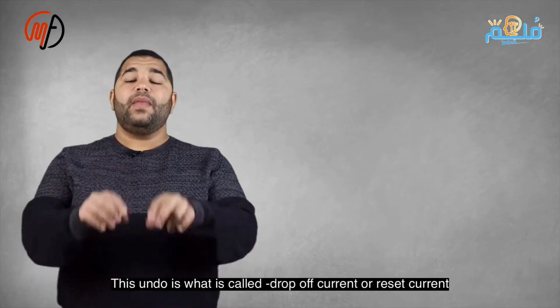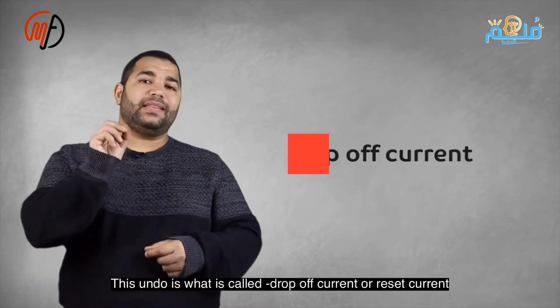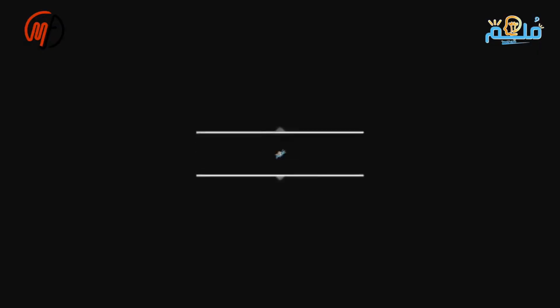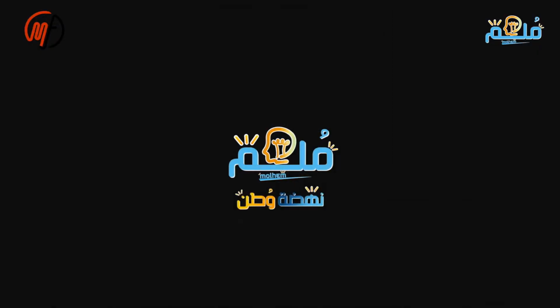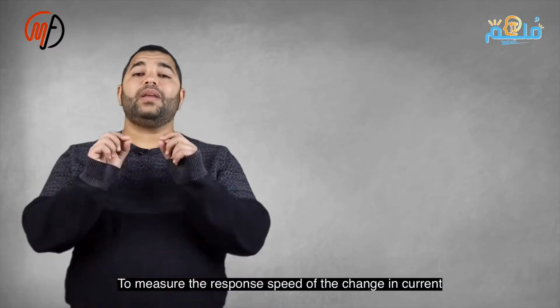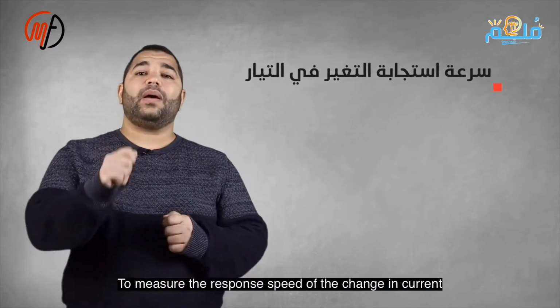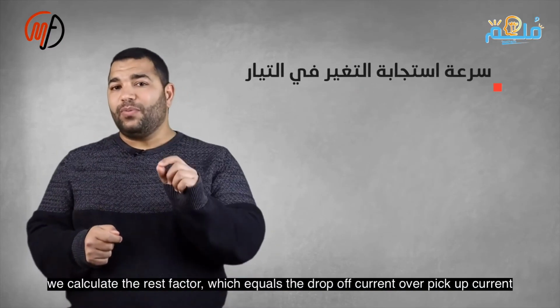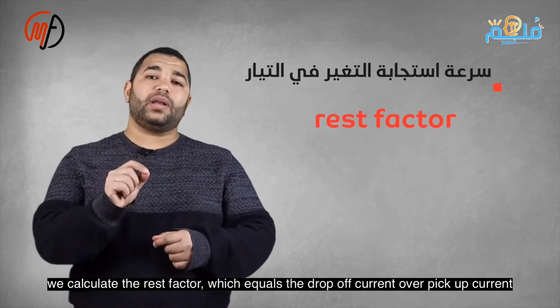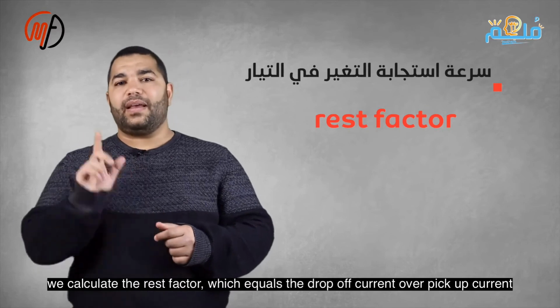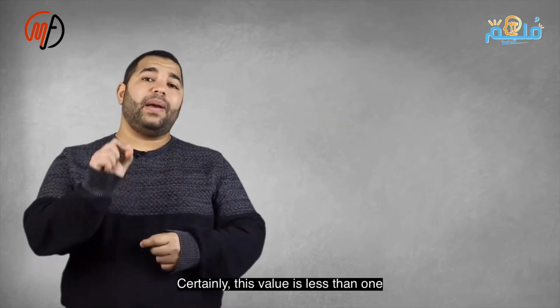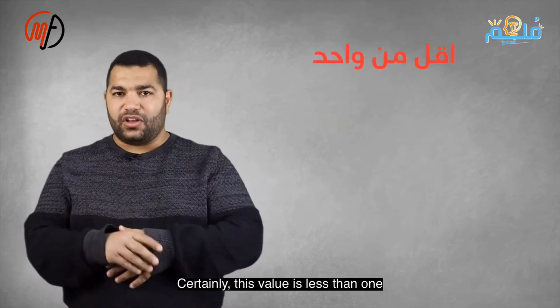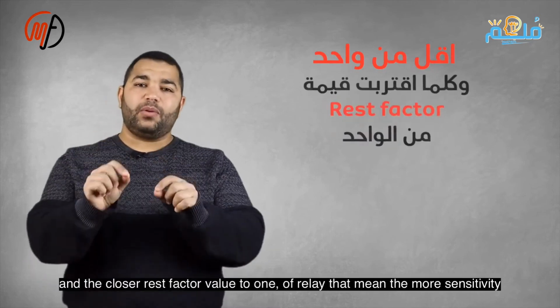The second test for the overcurrent and earth fault relay is the timing test. To measure response speed to current changes, we calculate the reset factor, which is drop-off current over pickup current. This value is less than 1. Closer to 1 means more sensitivity. If current is less than pickup current, even by 0.001, the relay should not operate. The reset factor is key for comparing relays.